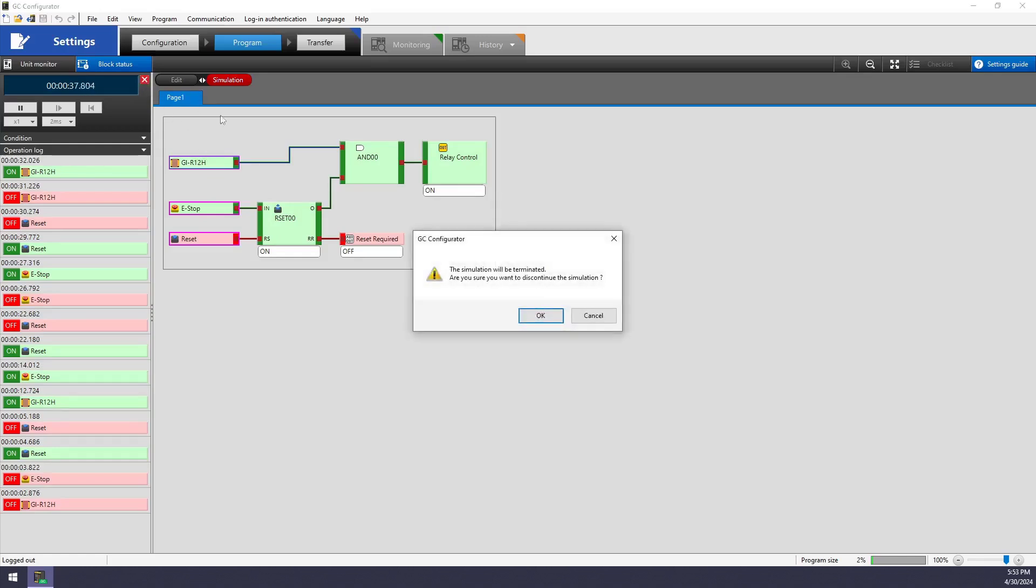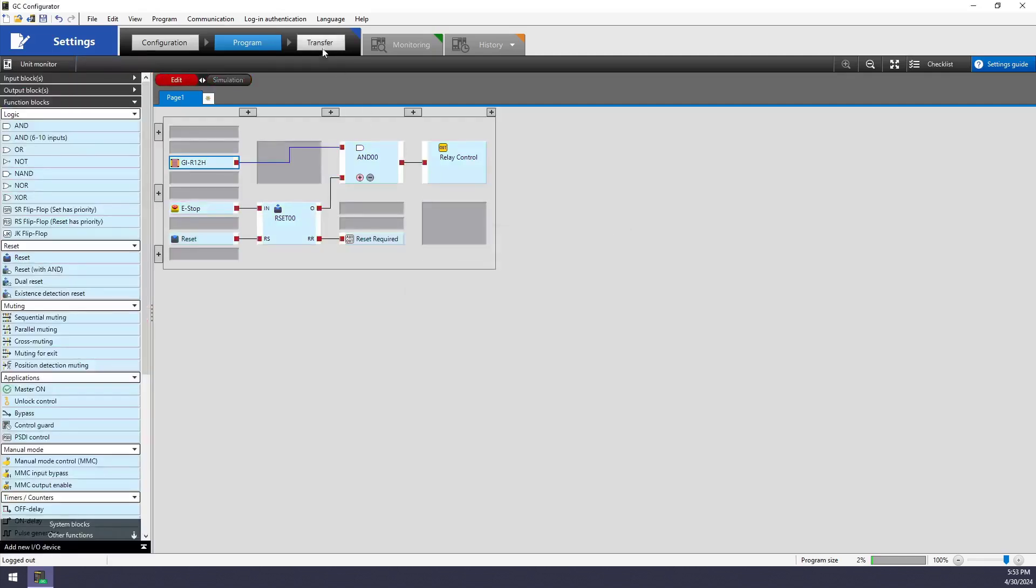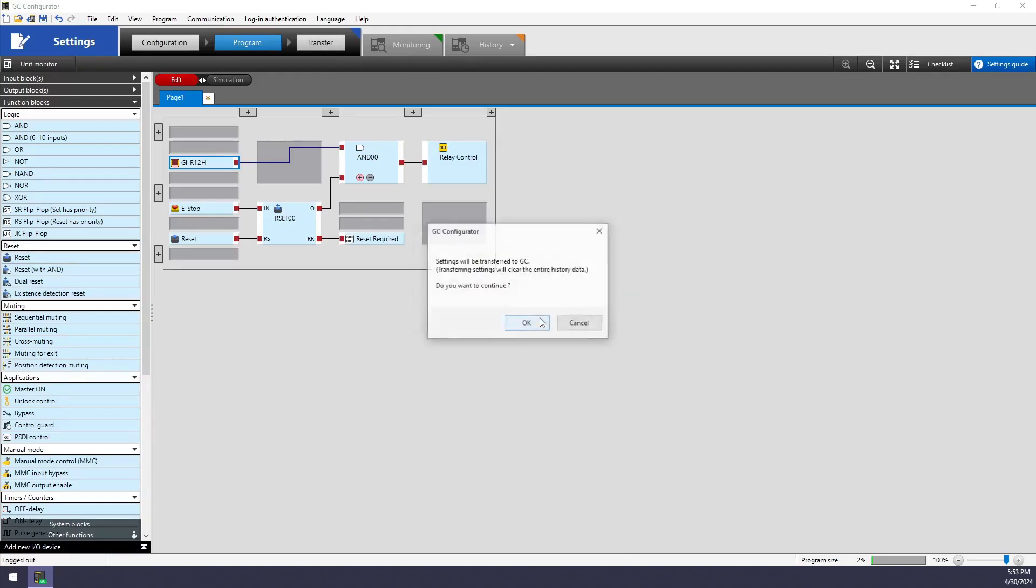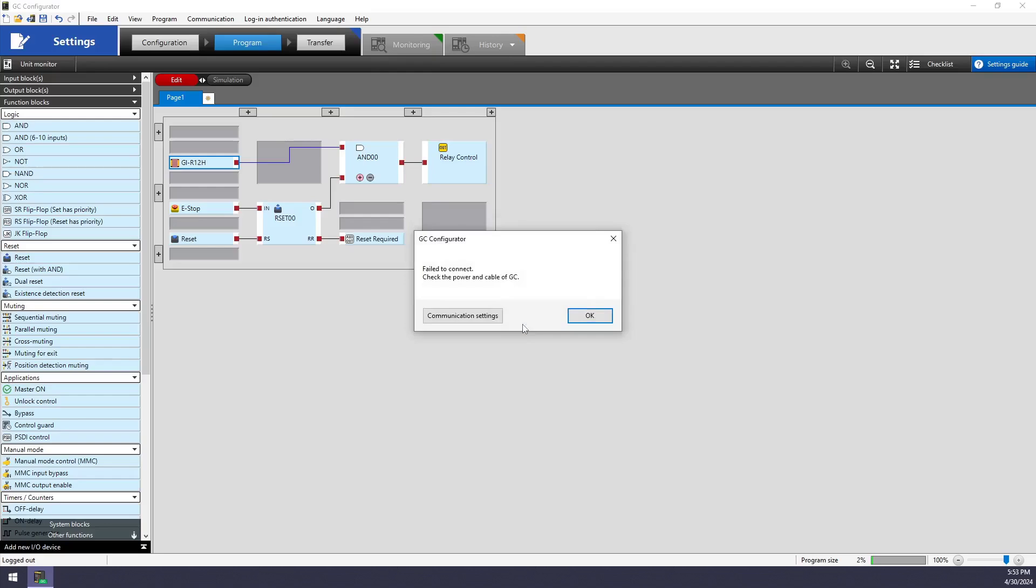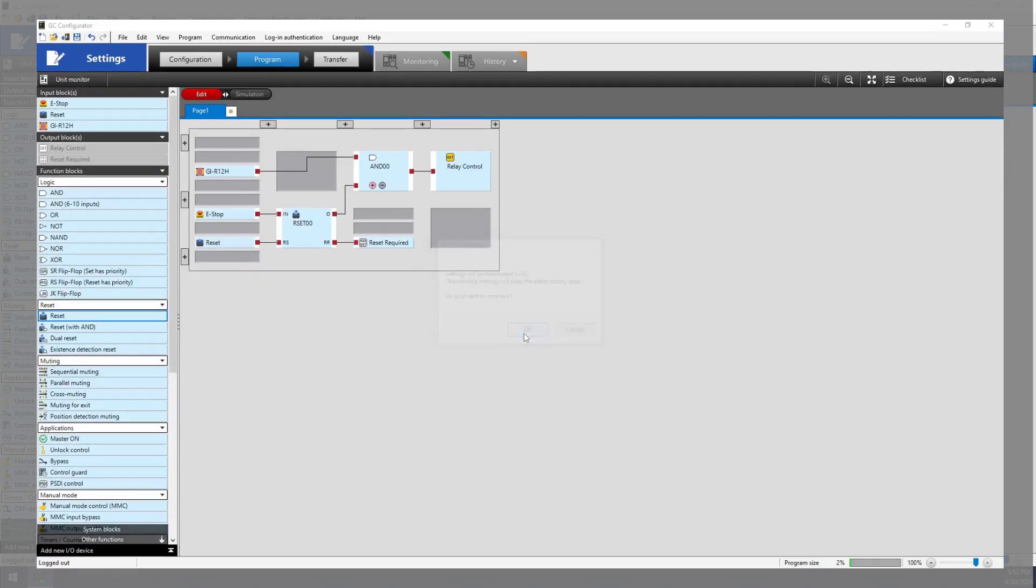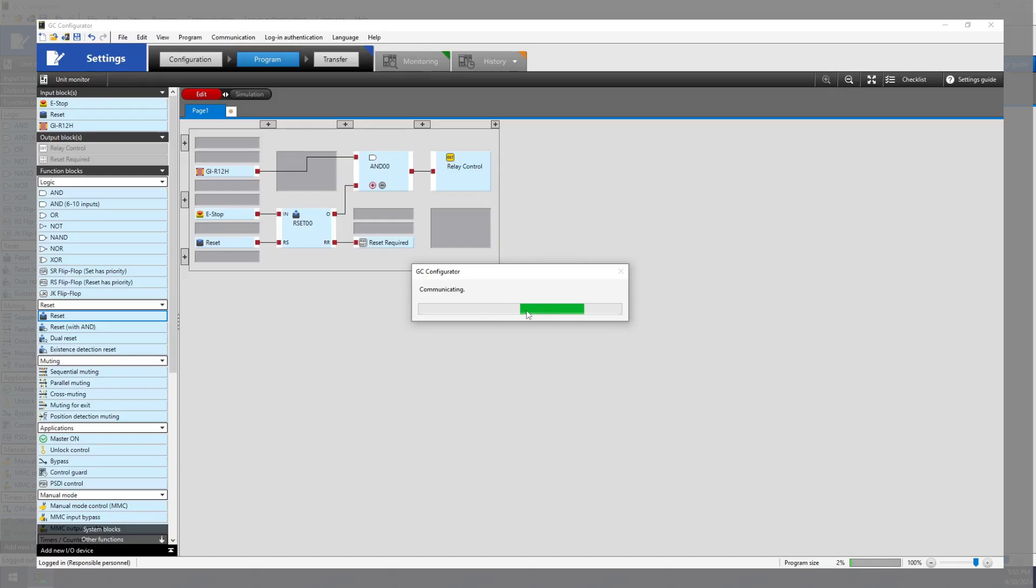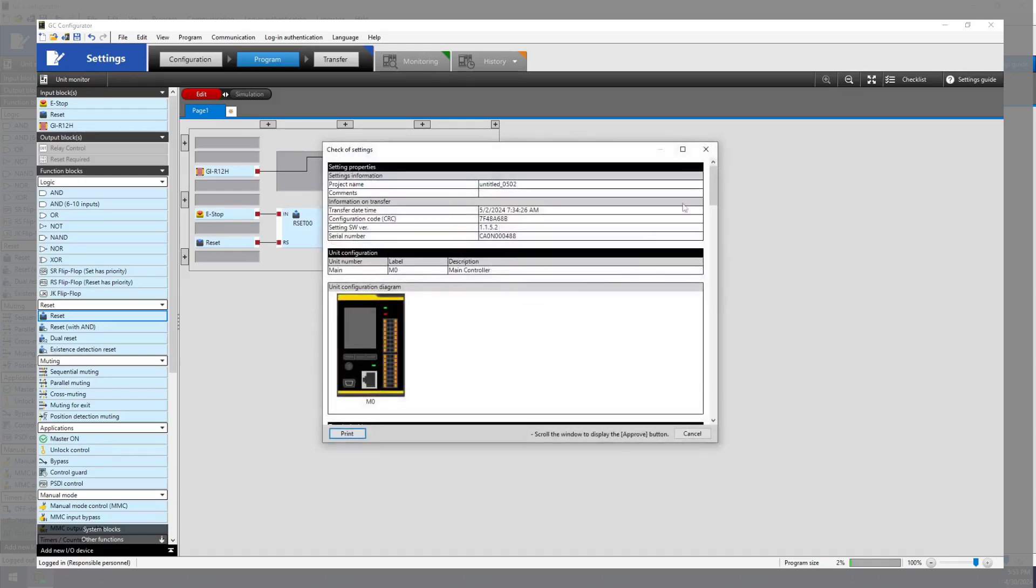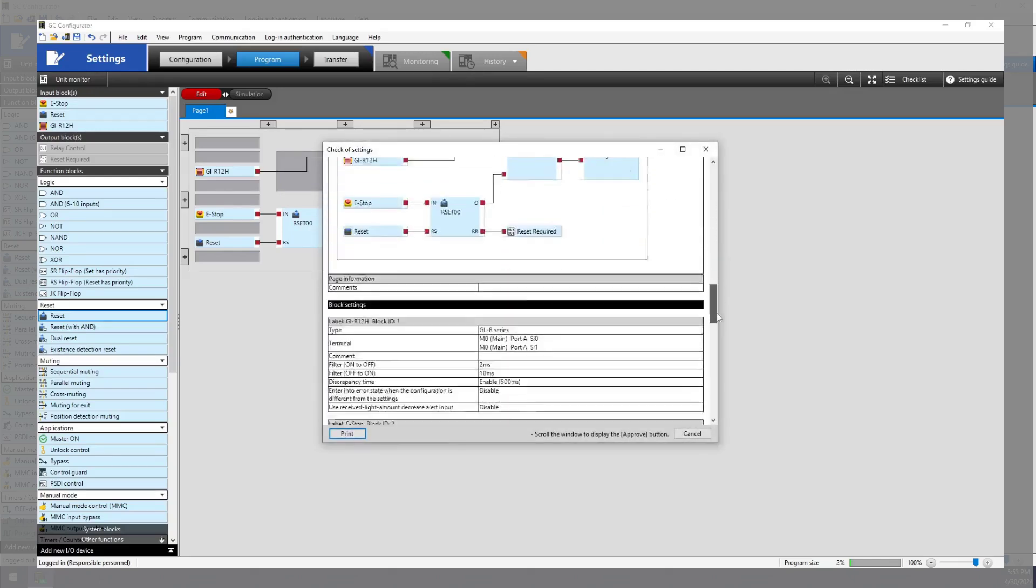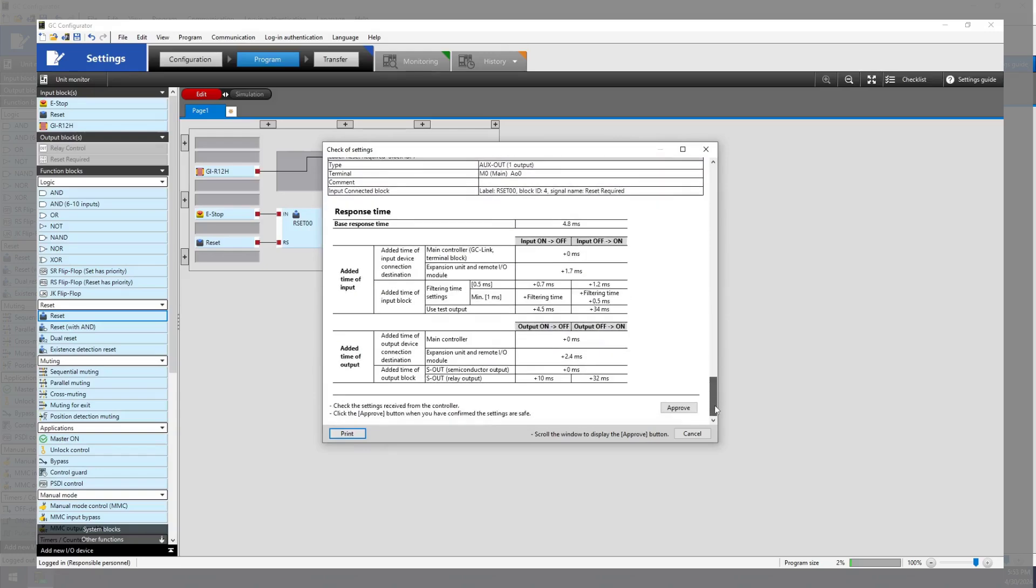So I'll finish my simulation and then click on transfer to send this program over to my GC1000. You can press yes to save it on your computer. I'll press no and then you transfer this over to the GC. Now I don't have a GC1000 connected right now, but if I did, it would ask for me to enter a password, which is a default 1111. And then I would have to scroll to the bottom of a settings report and press accept. And then the transfer will take place and I'll be able to set my GC to run mode.